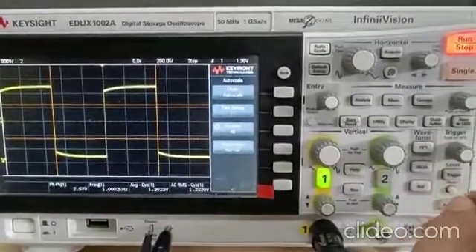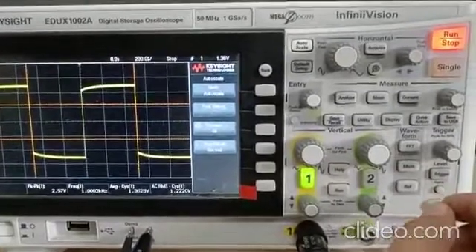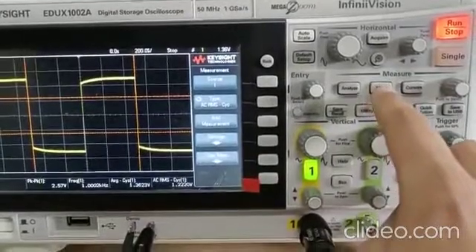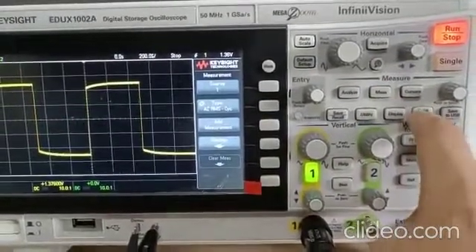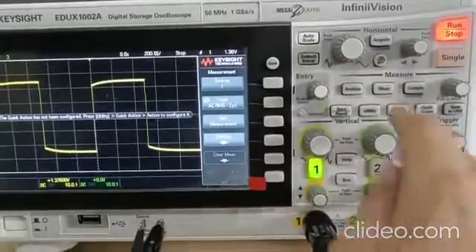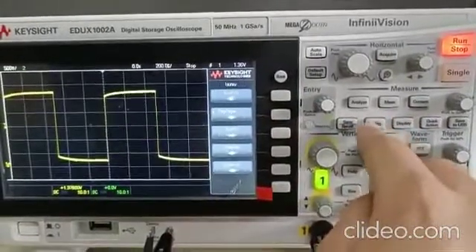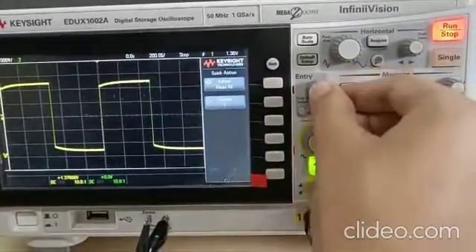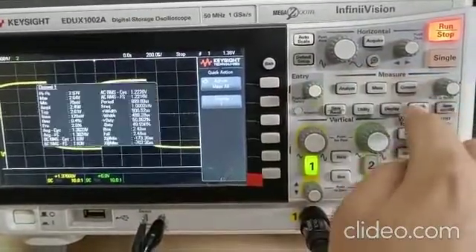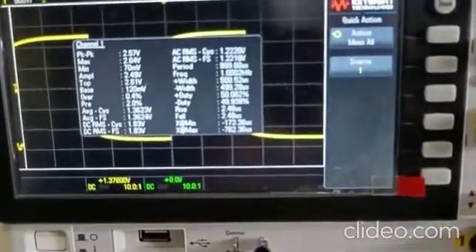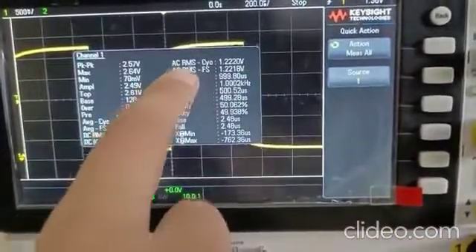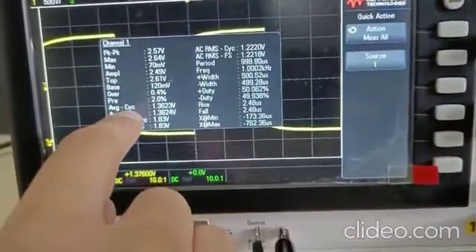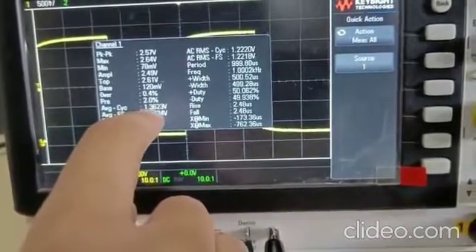To measure the average voltage of the waveform, we use measurement button and quick action. To quick action, we need to press utility, quick action, and we need to select measure all. AC RMS cyclic is 1.22 volt and average voltage is 1.36.